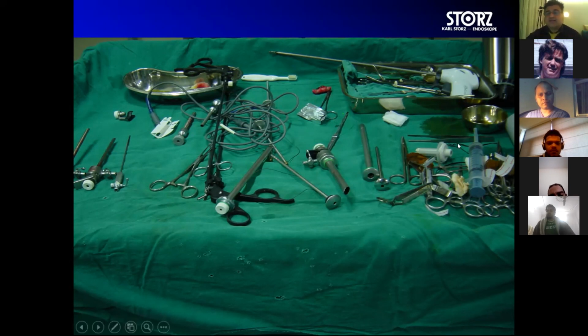We also supply special brushes which can go through these small shaft openings and through your neuroendoscopic sheath, and they can clean. Routinely, they usually have a toothbrush type of thing, which only cleans the surface, and that is not enough. So there are special brushes, which I will show you at the end of the presentation. By getting these accessories, which are not expensive, the life expectancy of the equipment increases. If we do not clean the tip of these forceps jaws, there are laser welded rivet joints. Once corrosion happens and you hold a tissue, maybe a little tough tissue, for the tensile strength of the instrument, and you grab it, the rivet joint breaks. And then these repairs are expensive. So this is a precaution.